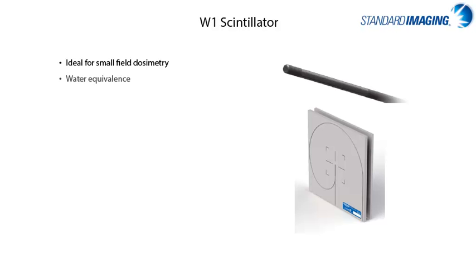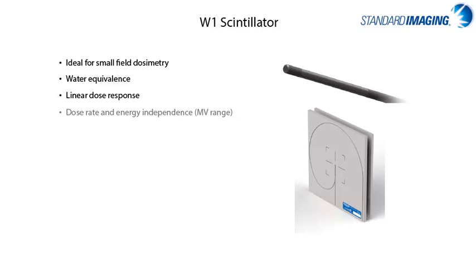This instrument is ideal for small field dosimetry, as it is water equivalent, has a linear dose response, is dose rate and energy independent, and there is an automatic Cherenkov correction applied to the measurements when the scintillator is used with the supermax electrometer.